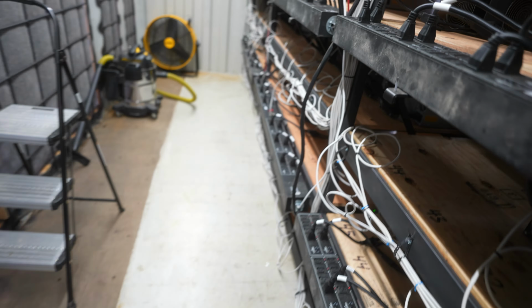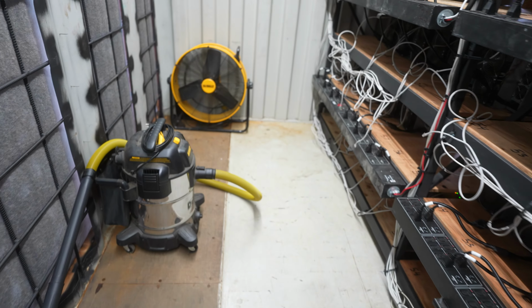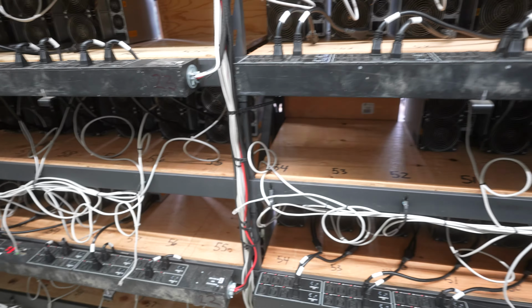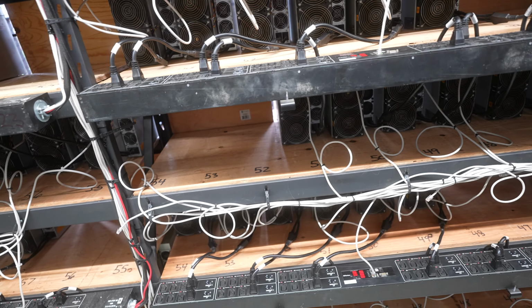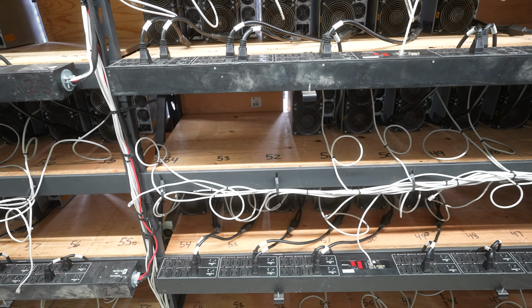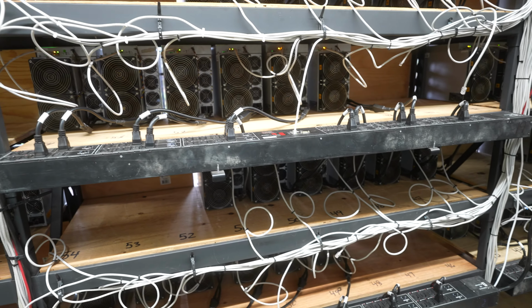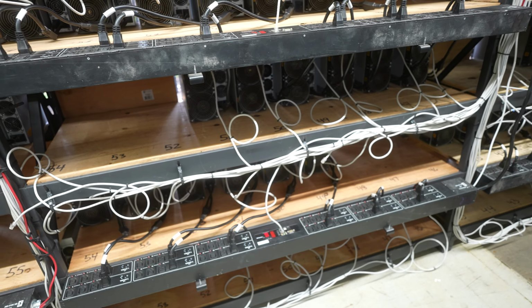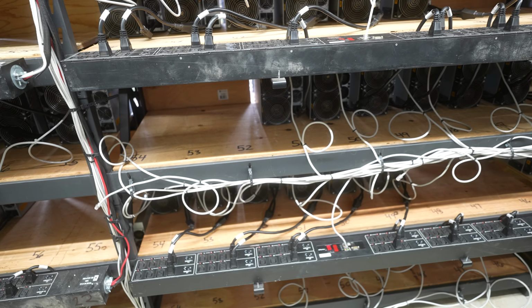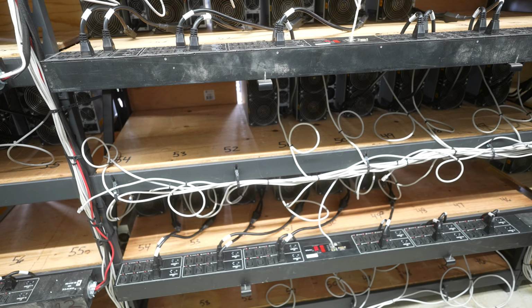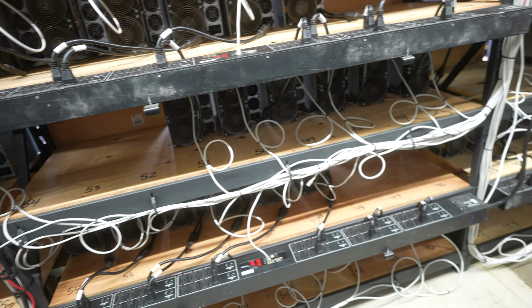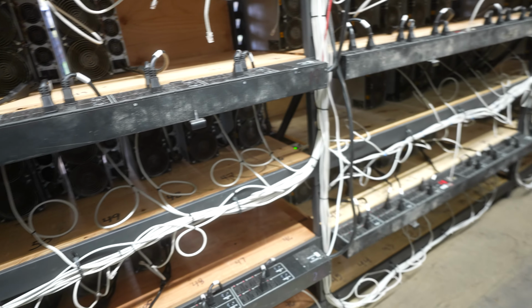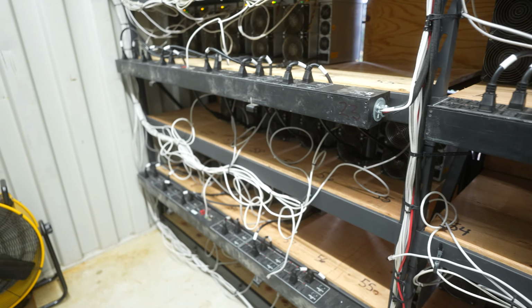Now, there are other PDUs we have at a different farm. Most PDUs are run by sharing phases, running like A, B, A, C, and so on. One of our other farms has that setup. For those PDUs you have to do different math. You have to make sure that when you're loading it, you write down on the breaker, hey this is AB, hey this is BC, hey this is CA, and so on.